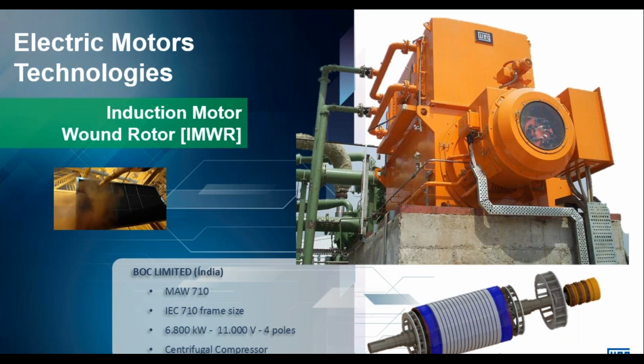And here you also have an effect where the starting torque of the machine is directly proportional to the torque of the load, and the same applies to the current of the machine during startup. One interesting thing to consider here is the use of brushes. So from an OpEx or operating point of view, there is some maintenance required, some brush replacement. And one additional thing to think about is the dust buildup.